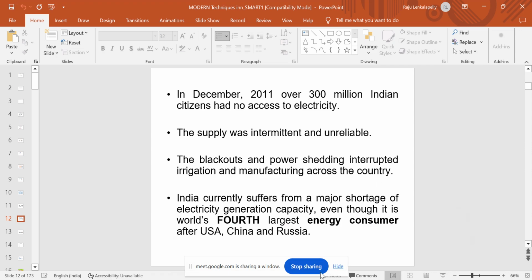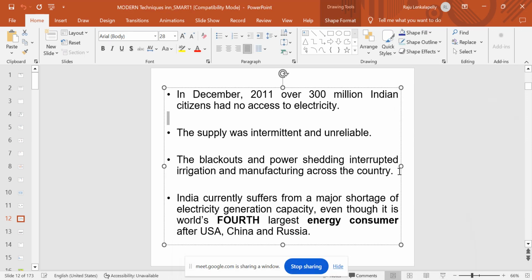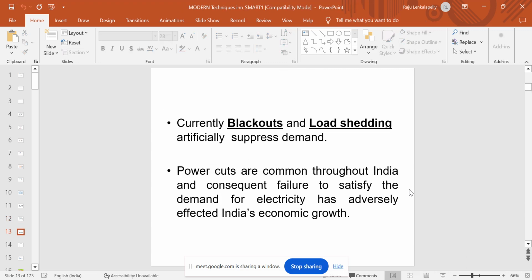In this one, on July 30th and 31st, 2012, northern India experienced blackouts on both days. There were several reasons for the blackout; one of them was low frequency. In olden days we used to maintain frequency as well as voltage within plus or minus 5%. But because of the 2012 blackout, we still keep voltage at plus or minus 5%, but frequency is no longer plus or minus 5%. The lower frequency limit is 49.5 and upper is 50.2. So electricity boards maintain strict discipline of frequency.